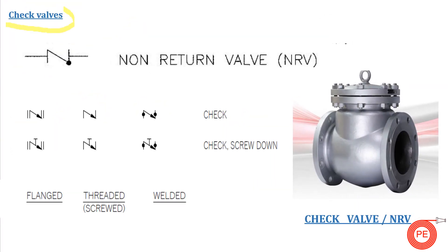The next valve is the check valve or non-return valve. For the non-return valve, you can see there is a 45-degree angle but the dot is shown at the edge, whereas in butterfly valves the dot is in the middle of the line — this is the basic difference between them. In some companies the designer shows an arrow instead; both symbols stand for a non-return or check valve. Again, two lines indicate flanged, nothing indicates threaded, and two dots indicate welded connection.